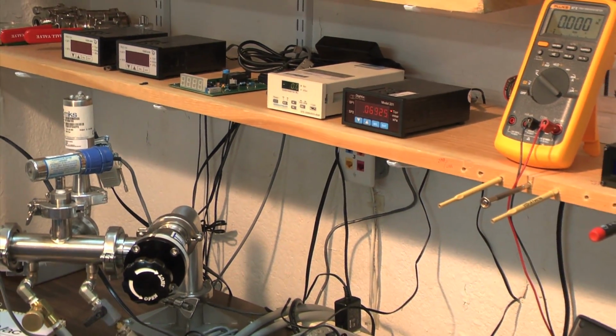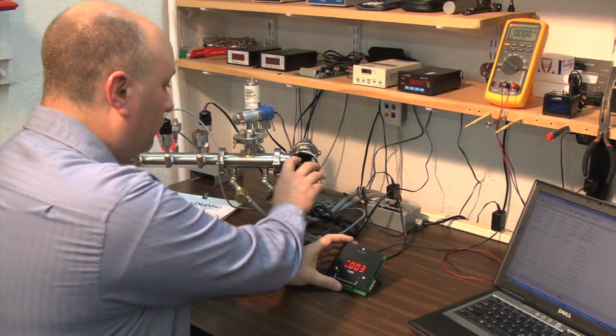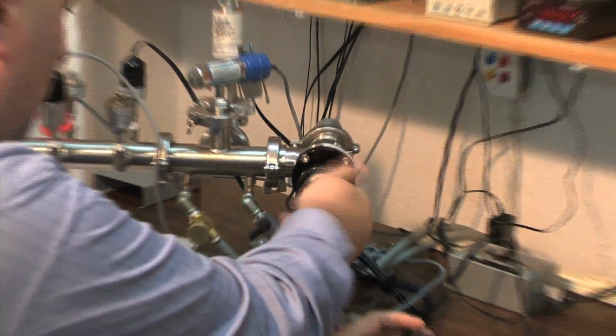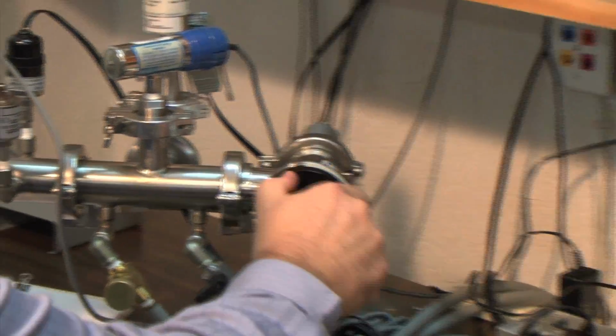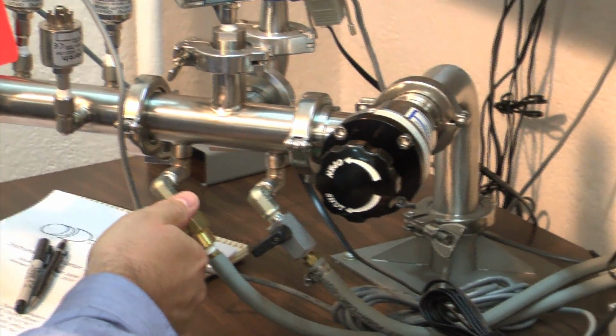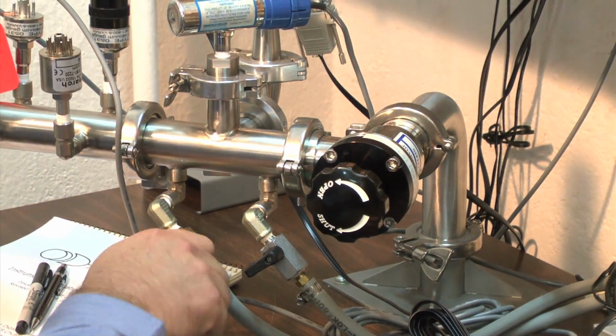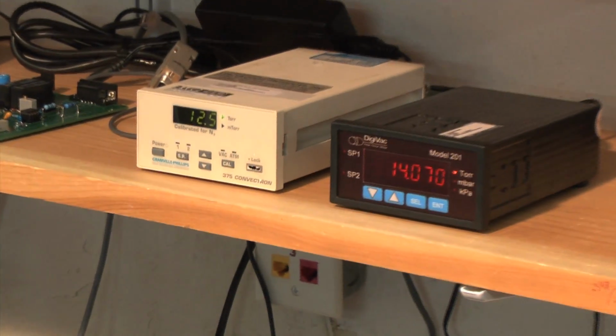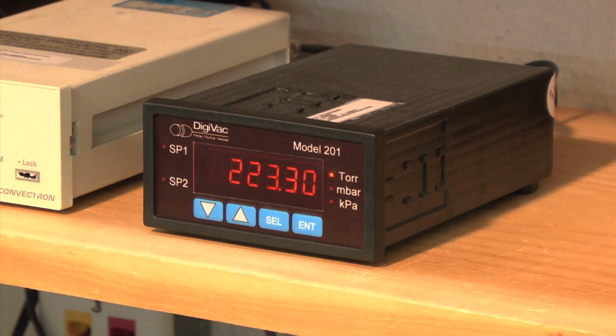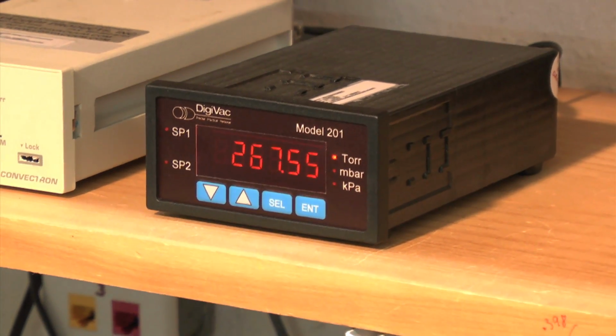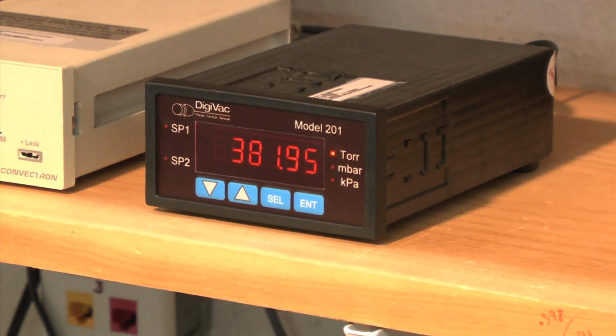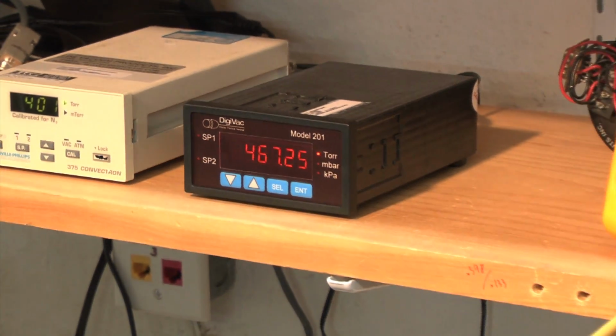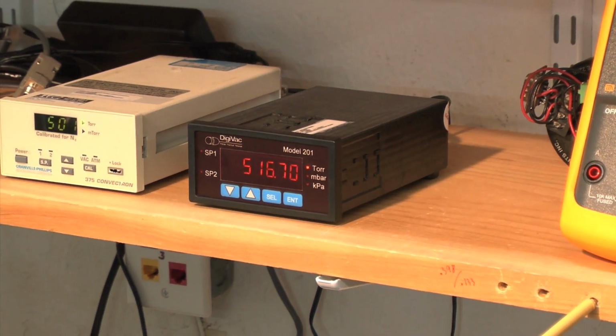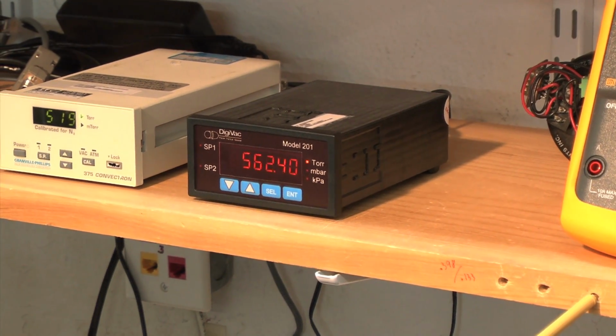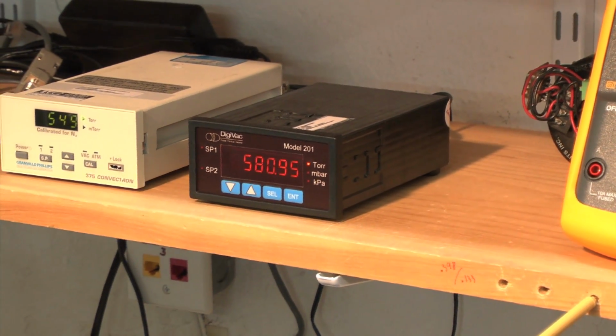Our first step, once the instrument is plugged in, warmed up, and stabilized, is to stop our vacuum system and purge the system using dry nitrogen to approximately 600 torr. The 600 torr reading will be indicated by our Baratron when it reads 600.0. Now we can calibrate our 801W at any pressure higher than 500 torr. We certainly do not want to calibrate at atmosphere because atmospheric number changes on any given day. For good practice, we like to use 600. We'll approach that.